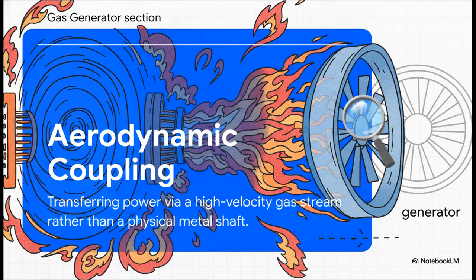The secret here is aerodynamic coupling. There is absolutely zero physical metal shaft connecting the gas generator section over to the power turbine section. None. Instead, the gas generator just blasts a massive high-velocity stream of hot gas, and the power turbine acts like a giant windmill catching that exact stream to turn the generator. Because they aren't bolted together, the power turbine stays steady at 3,600 while the gas generator revs up and down on its own. It's a brilliant design, and it completely eliminates the need for some massive, heavy speed-reducing gearbox.